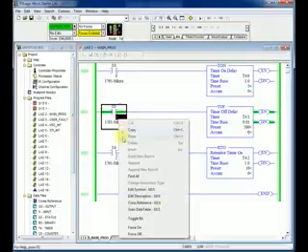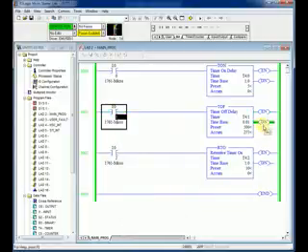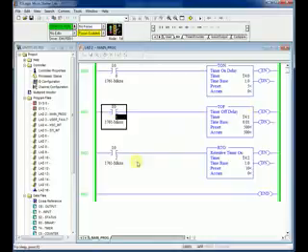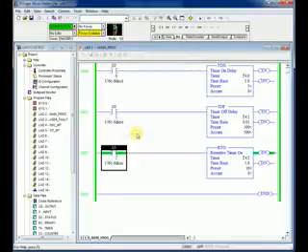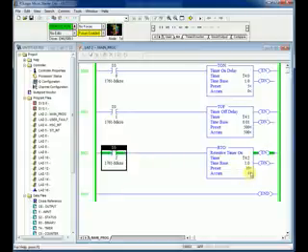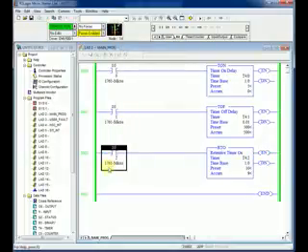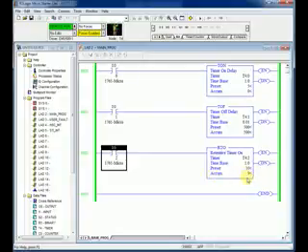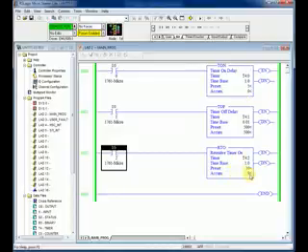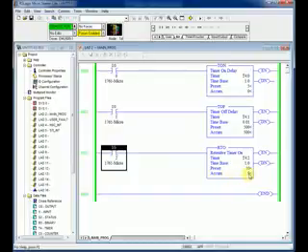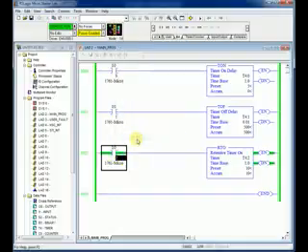Now let's see retentive timer on. When I will put this to on, it counts seconds and I put the delay of 10 seconds. When I will put it off, you can see that I put the input off, the accumulator stops but doesn't reset to zero. You can see in TON timer, when the input is zero, the accumulator is set automatically to reset. But here the accumulator doesn't reset. When I will start this again, the accumulator will start from nine, and after one second it will get activated. In one second you will see the done bit. But when you will put it off, it will not get done bit zero. As I told you, you need to reset this timer to clear this done bit.